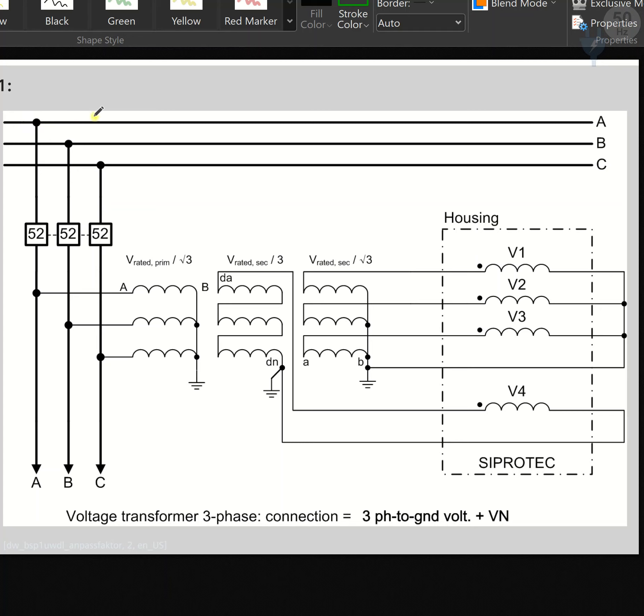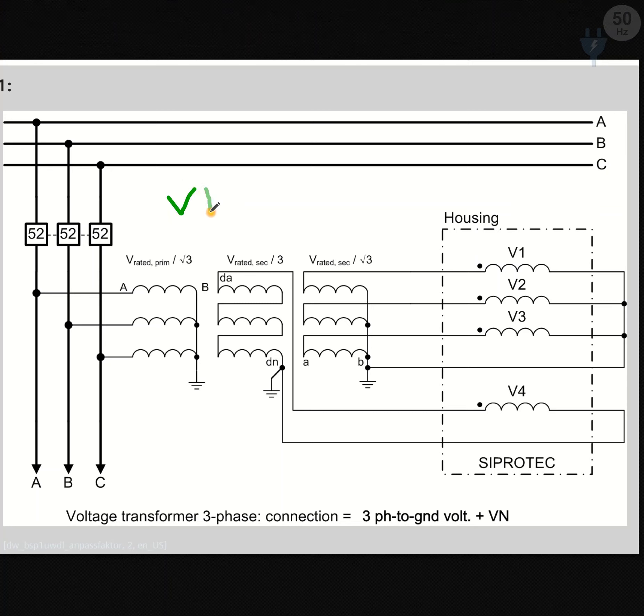Suppose we have a bus bar here, and this is a feeder connected to this bus bar which we want to protect. We have connected the PT, or we call it a VT, to this feeder or transmission line. The primary is connected in star, and the secondary phase windings are also connected in star and connected to the relay. This is our relay — these are the VT connection terminals and this is the neutral connection to the relay.